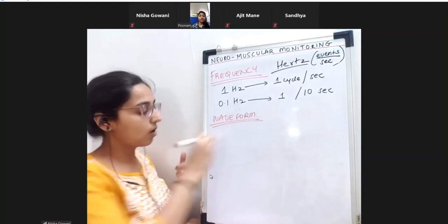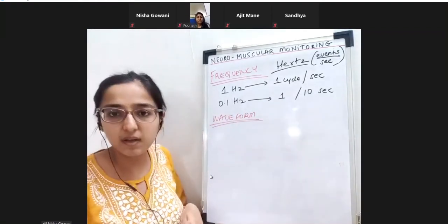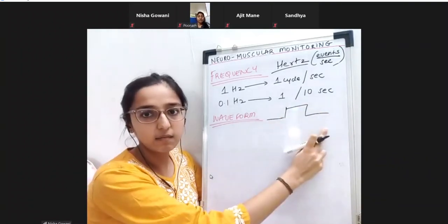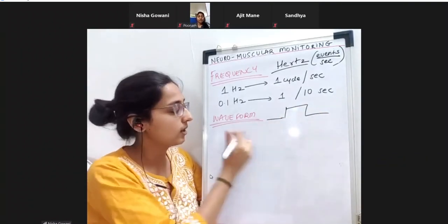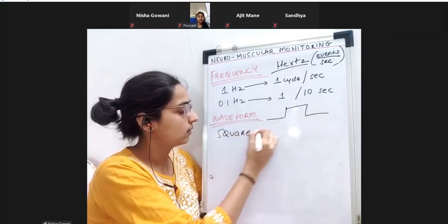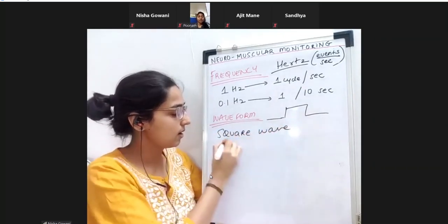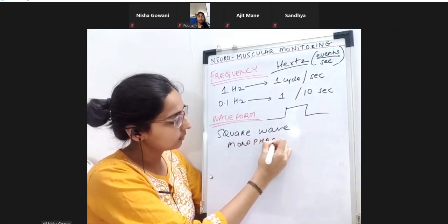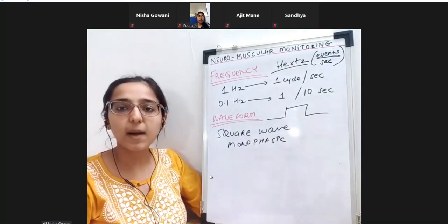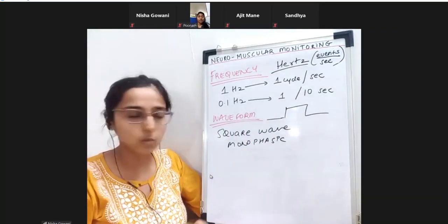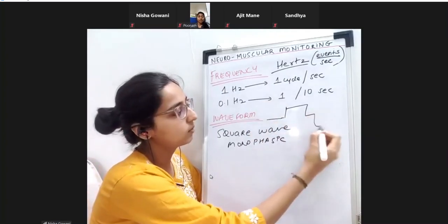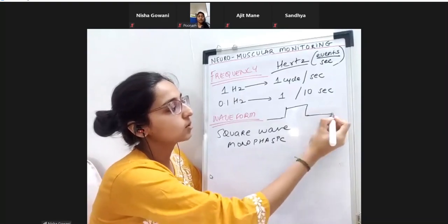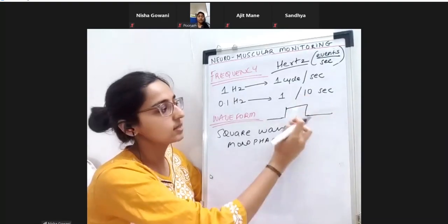What is the waveform of the current we are delivering? The waveform from a nerve stimulator is a square wave, and it is monophasic - going only in one direction. If it were biphasic, the picture would look different. We only need to remember it is a monophasic square wave pattern.